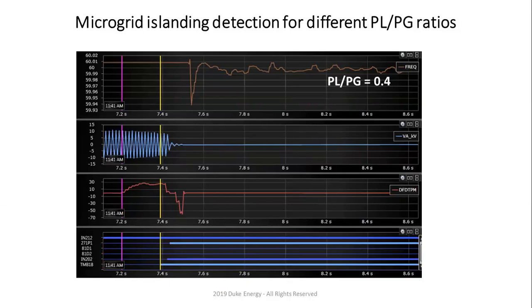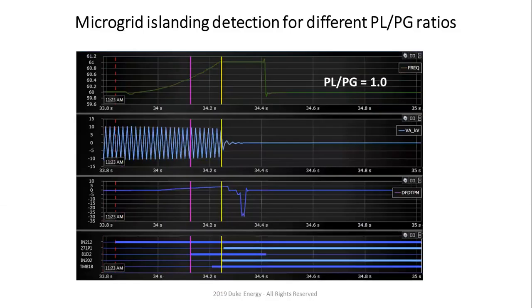This is just to show what happens during the islanding, and then how does DF or 81R, rate of change of frequency settings act, right? Here's the same thing for PL over PG equal 1.0, right? You can clearly see on the left side input 212. Again, that's us pressing the button on POI to open the upstream recloser. 27P1 is essentially when islanding would be detected by the undervoltage. 81D2 is actually showing when the islanding was detected by the overfrequency, right? But then you can see clearly that DF over DT has changed a lot depending on where we are in this whole scheme, right?